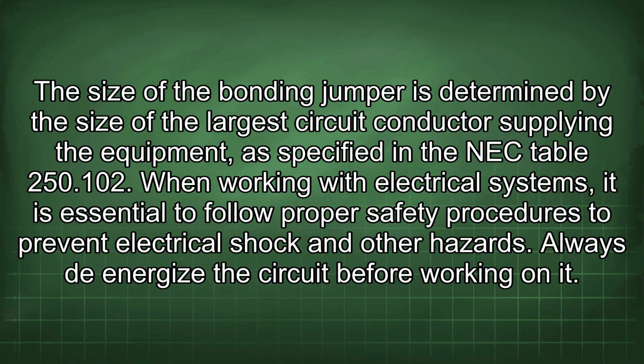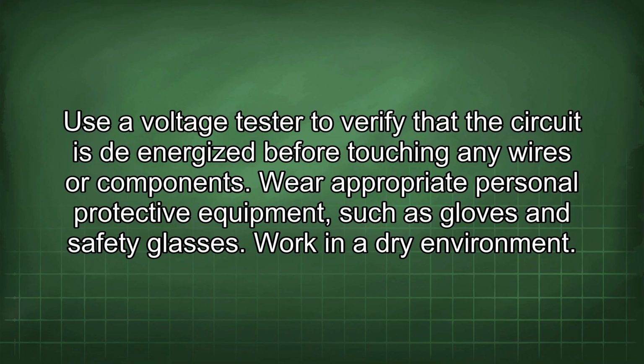The size of the bonding jumper is determined by the size of the largest circuit conductor supplying the equipment, as specified in NEC Table 250.102. When working with electrical systems, it is essential to follow proper safety procedures to prevent electrical shock and other hazards. Always de-energize the circuit before working on it. Use a voltage tester to verify that the circuit is de-energized before touching any wires or components. Wear appropriate personal protective equipment, such as gloves and safety glasses. Work in a dry environment.